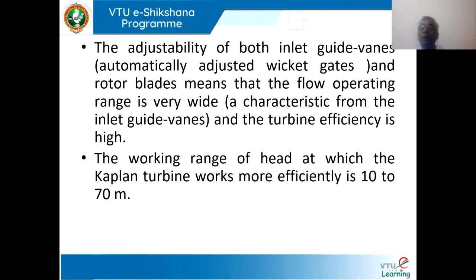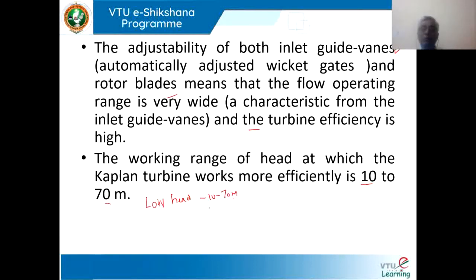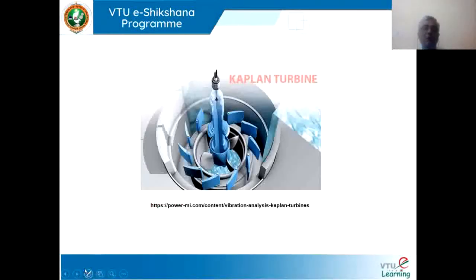The adjustability of both guide vanes and rotor blades means the operating flow range can be varied widely by the action of both the guide vanes and the runner vanes. Generally, the working head of a Kaplan turbine varies between 10 to 70 meters, because it is a low-head turbine. This is the general specification.